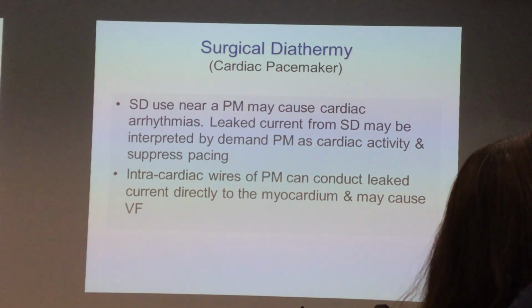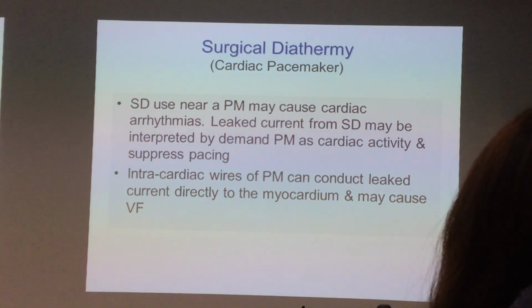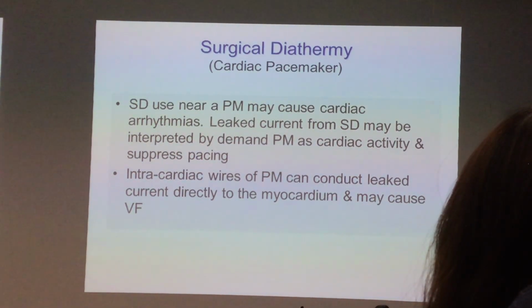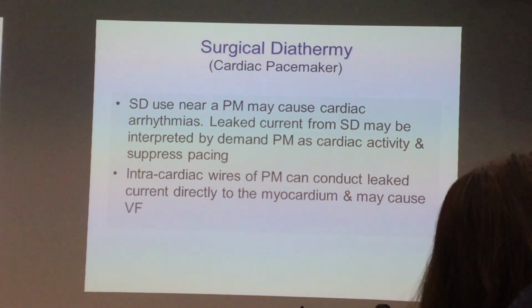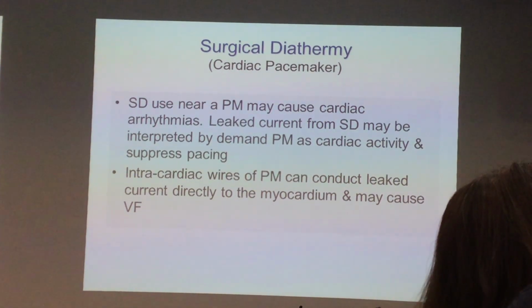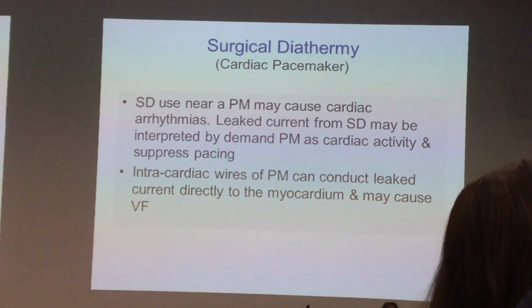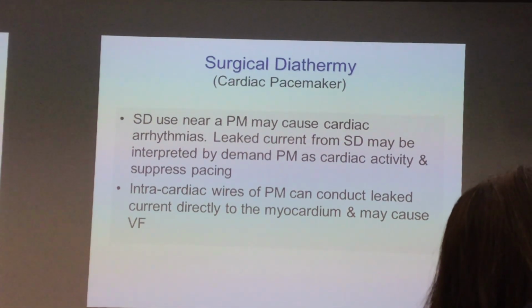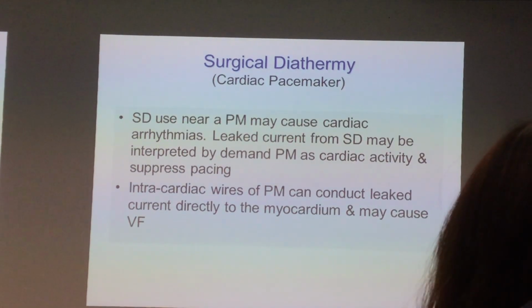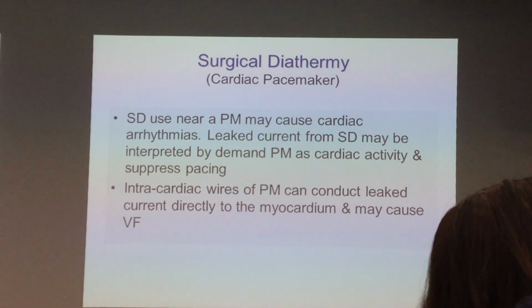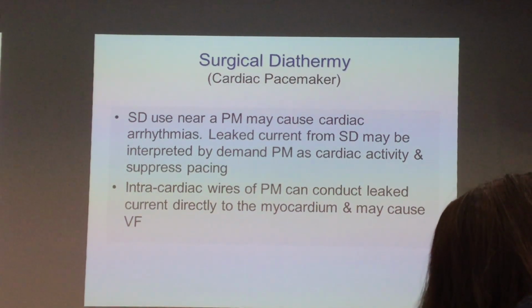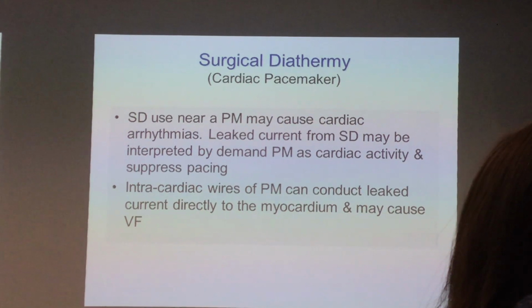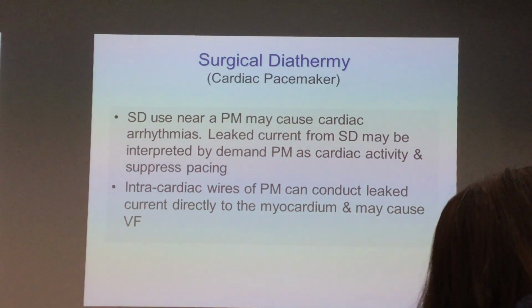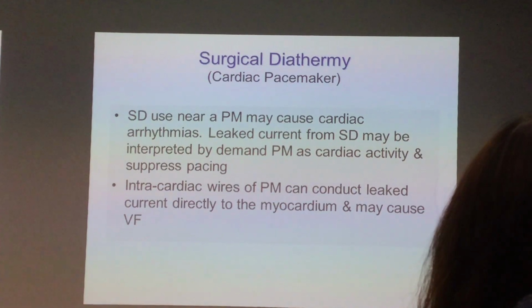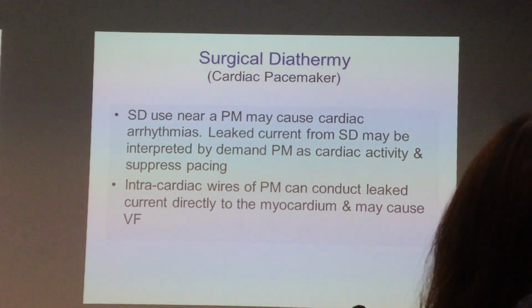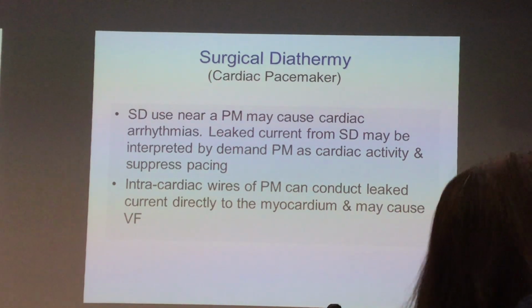So the pacemaker can get wrong information, an additional signal which comes from the diathermy. The pacemaker gets two signals, one from the pacemaker side, one from the diathermy. So it may get confused. It may not function. Unipolar diathermy can affect the function of the pacemaker because it may receive an additional signal from the diathermy that it will interpret differently.